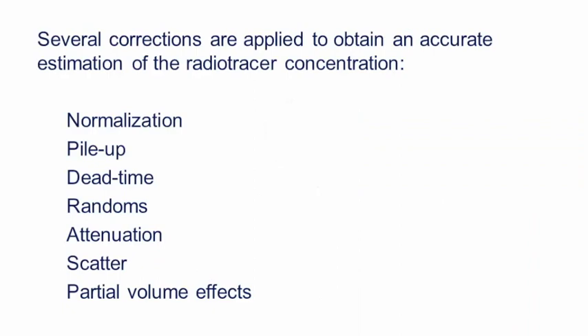There are a number of other corrections that need to be done in PET. There's normalization, where quality controls are done generally every day and a large stability scan every few months. There's also pileup, dead time corrections, and partial volume effects in PET — similar to MR but with different physical principles.